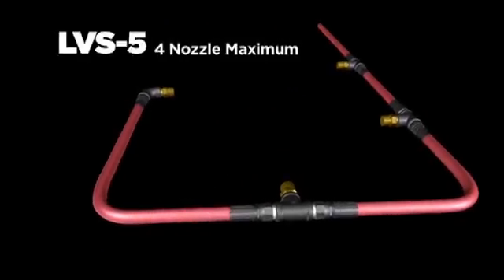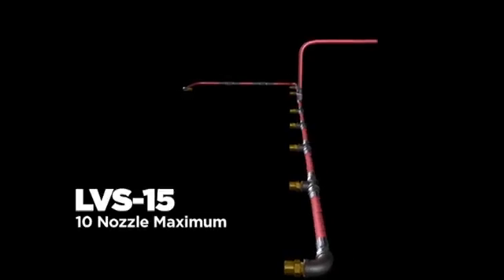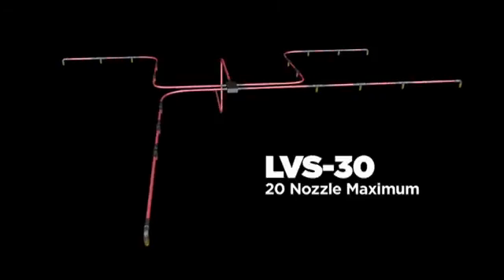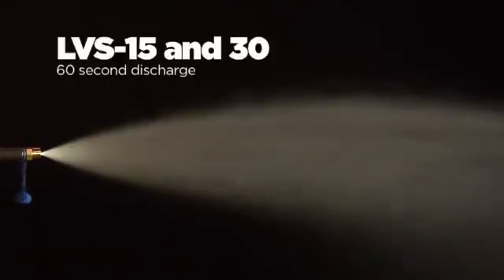The LVS-5 allows for a maximum of four nozzles of protection. For larger equipment, the LVS-15 and LVS-30 can be configured to a maximum protection scheme of 10 and 20 nozzles respectively. The Ansul Liquid Vehicle System provides constant nozzle pressure and a full discharge pattern throughout the duration of the discharge — a full 30 seconds with the LVS-5, while the LVS-15 and LVS-30 will discharge for 60 seconds.